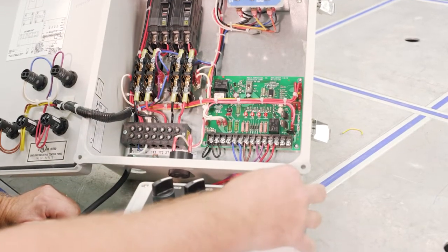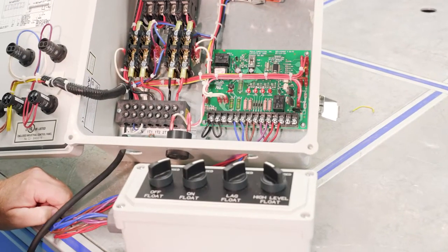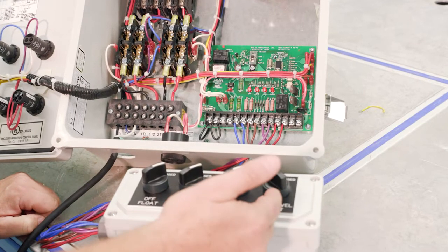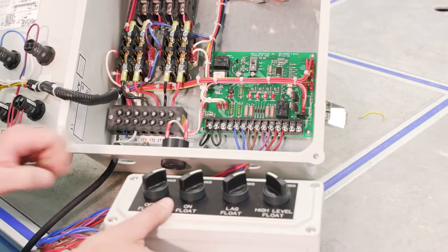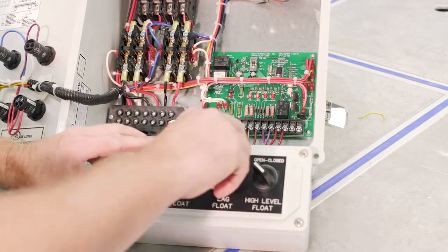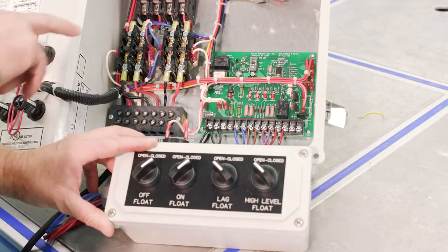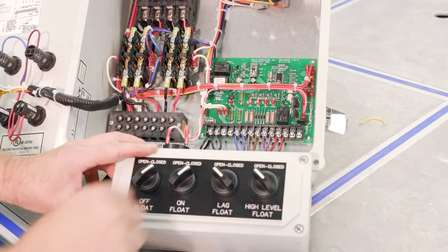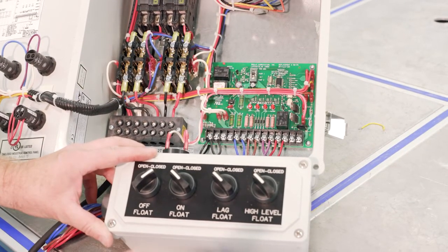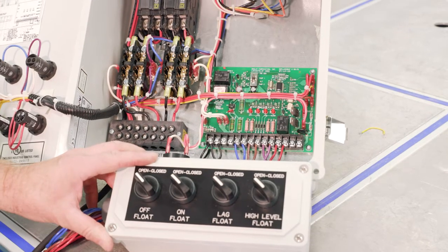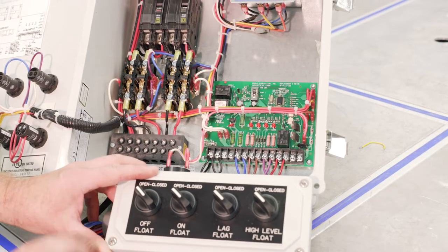Okay, so now I got everything on, again so we're going to go backwards now, that high level opens up, the lag float opens up, still have both pumps running, the on float, both pumps are still on, and then they won't turn off until it gets to the off float.